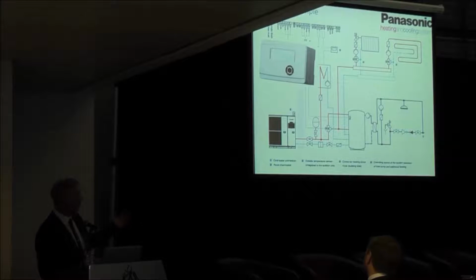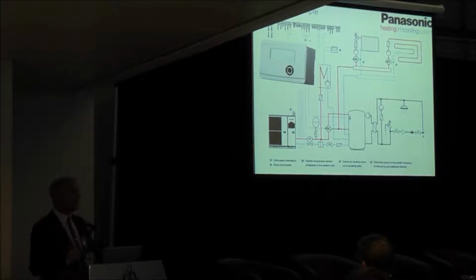If there's a certain amount of kilowatts coming from your PV system, you can then, while you're out of the house, switch on your heat pump and charge a heating system with a certain amount of water. If you have a large buffer vessel, or large storage for domestic hot water or for heating, you can heat the thermal store to a level far above your calculated set point. Okay, so you can heat the thermal store up to 70 or 80 degrees C while you're out of the house, using free energy from your PV. Heat pump manager can control that for you.